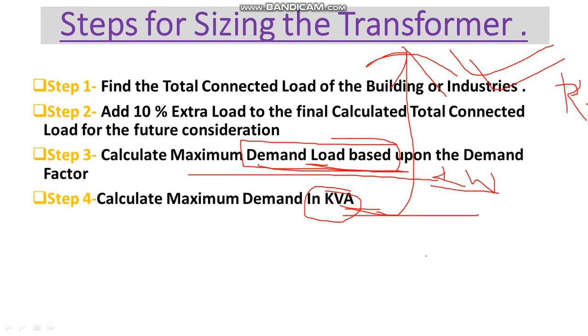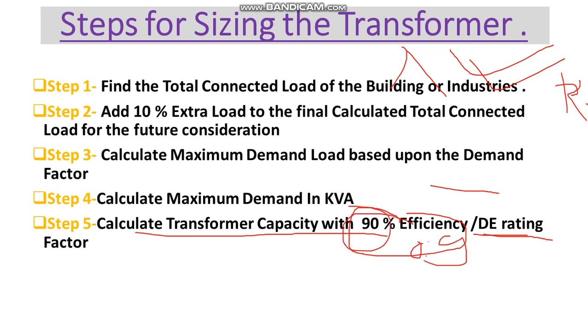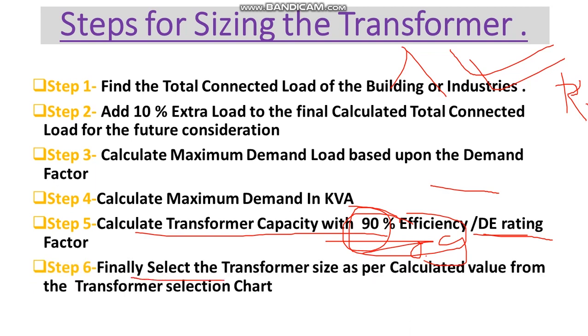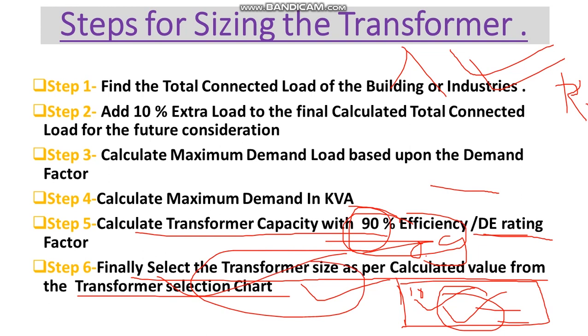In Step 5, calculate the transformer capacity with 90% efficiency, or we can say taking a derating factor of 0.9. Then finally in Step 6, select the transformer size as per the calculated value from the transformer selection chart, where we have ratings from lower to higher and we select accordingly.